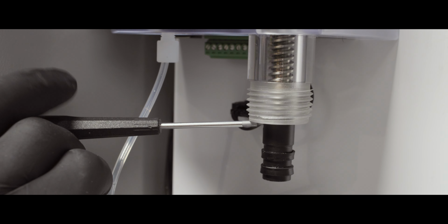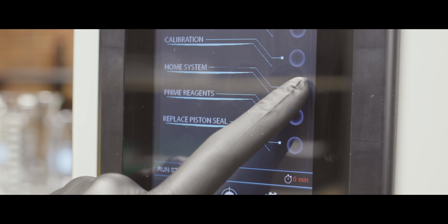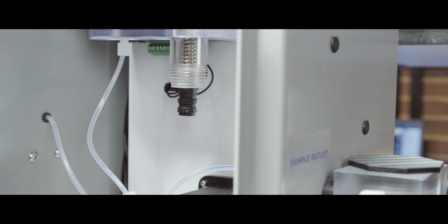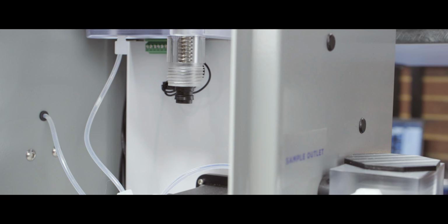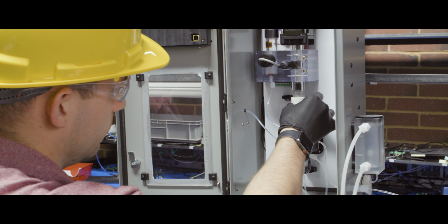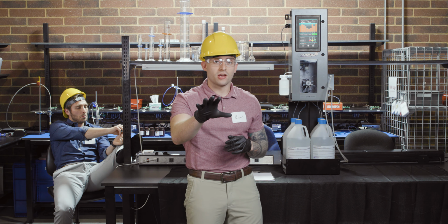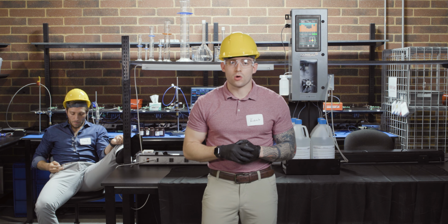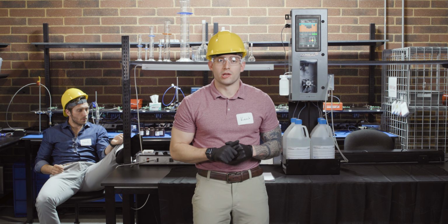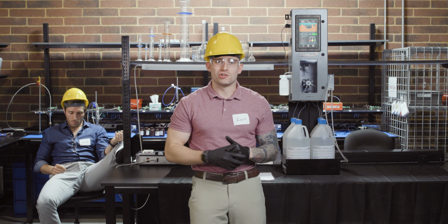Now, tighten the set screw. Step number 7, press Home System on the display to raise the piston seal. Step number 8, screw the threaded cap back on and reconnect the tubing. Once this is done, you're gonna wanna recalibrate your Narwhal to ensure that everything's working properly. Now, let's get to tubing.